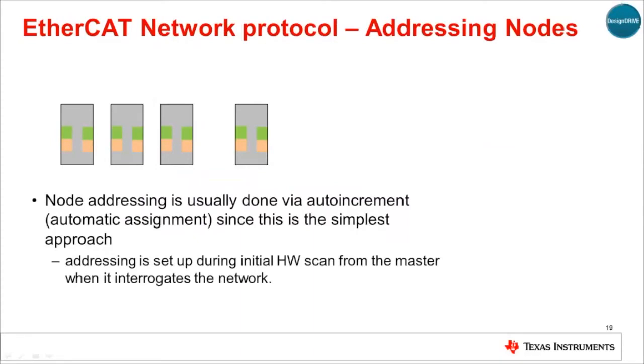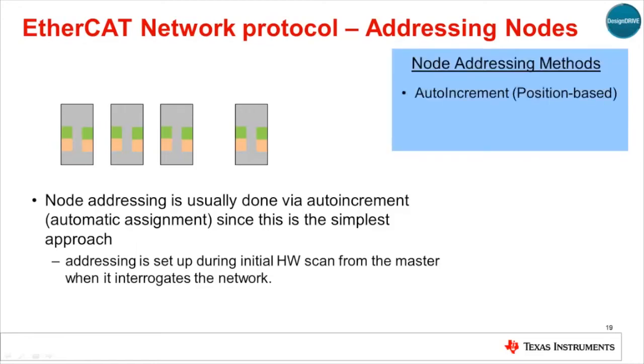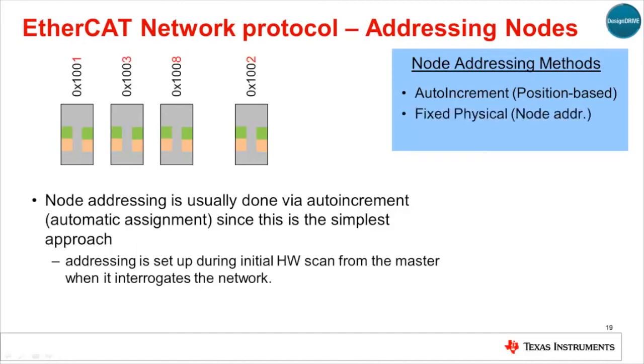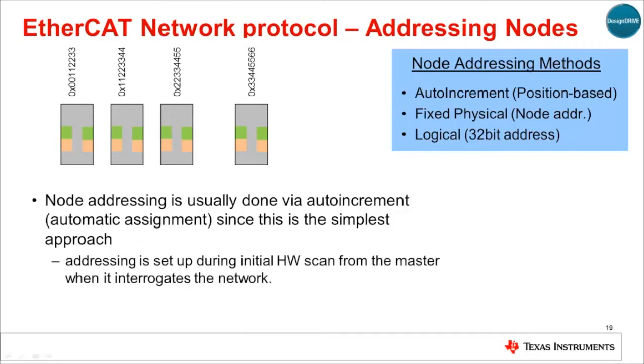The individual addresses of each slave node can be in any order specified by the master, and there are a number of methods of assigning addresses. Namely, AutoIncrement — a position-based method where nodes are assigned an address starting from zero and decrementing for each location in the chain — is the simplest and can be set up automatically by the master on the initial network configuration scan. Other methods include fixed physical addressing, also called node addressing, which is assigned during configuration scan and whose addresses can be independent of physical location in the network. Finally, there is logical addressing, which provides a 32-bit address rather than the 16-bit address of the other modes. Note that the 64K limit on node count in a network still applies.